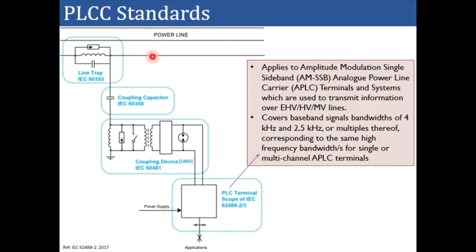Now let's see the various PLCC standards. You can refer to IEC 60353 for the line trap, IEC 60358 for the coupling capacitor, and IEC 60481 for the coupling device, that is our line matching unit.